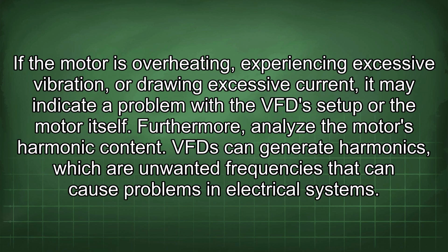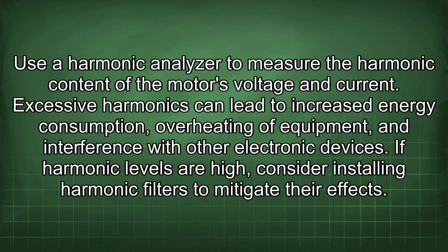Furthermore, analyze the motor's harmonic content. VFDs can generate harmonics, which are unwanted frequencies that can cause problems in electrical systems. Use a harmonic analyzer to measure the harmonic content of the motor's voltage and current. Excessive harmonics can lead to increased energy consumption, overheating of equipment, and interference with other electronic devices. If harmonic levels are high, consider installing harmonic filters to mitigate their effects.